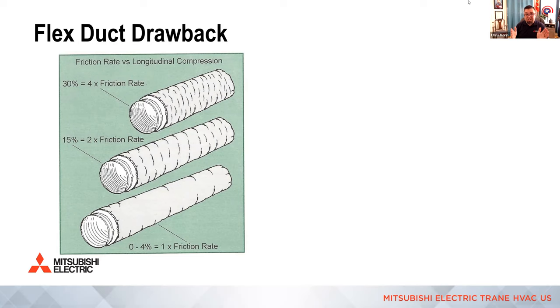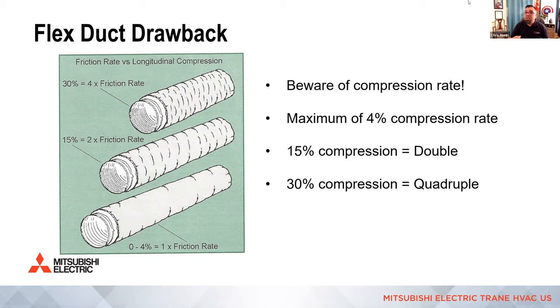Just 15% compression, you would have to double the friction rate in order to get that system to work. And what that means is a much larger size duct in order to get that same volume of air, because of all the pressure loss inside that helix with the poor compression. And 30% compression, which is what we see when people just pull it out of the box and don't pull that helix at all, would be four times your friction rate. It quadruples it, which makes the duct ridiculously large in order to get the same volume of air there.